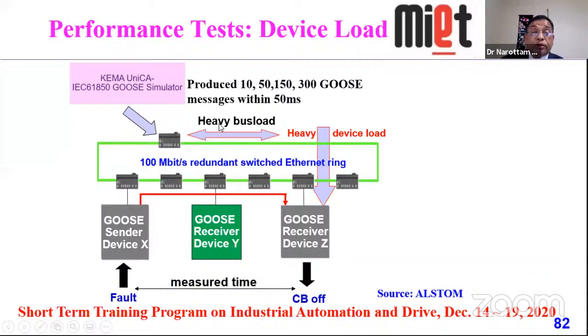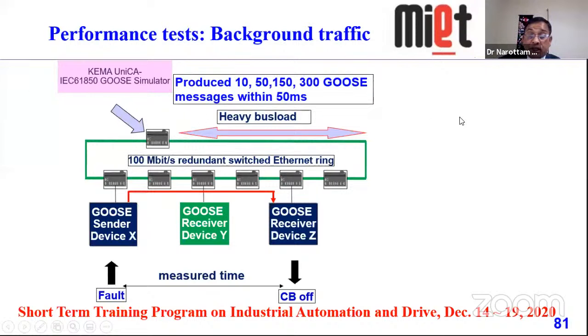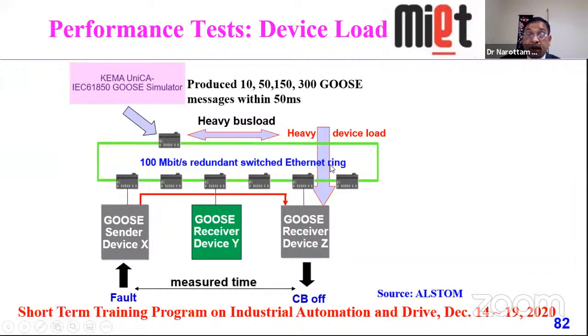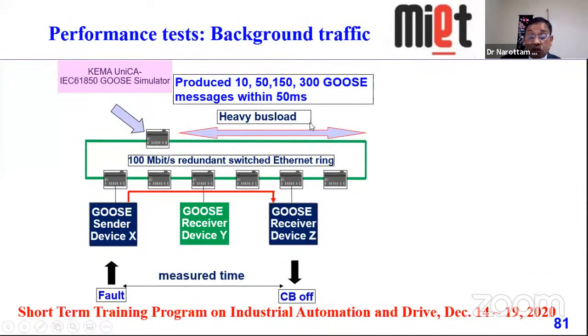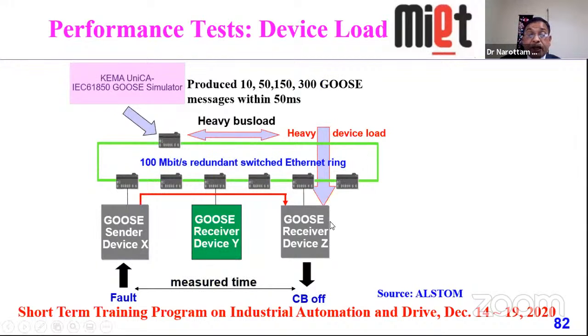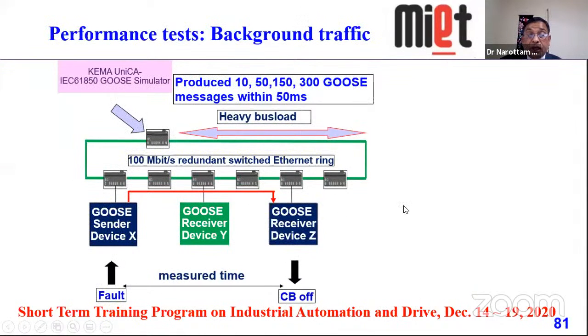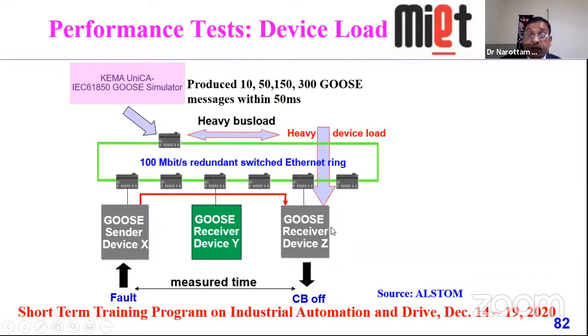Okay, and then we can, so far, yes. And now we are going for another set and then see the difference, because this is the simulator here, then this one simulator, and then heavy device load, because this is bus load, and this is heavy device load. Device is here. So far, in this case, also produce so many GOOSE messages within 50 milliseconds. And then heavy load is here, and then this is the fault, and then device receiver Y, this is device, and GOOSE receiver device in Z. If we compare here, we can see this is the heavy device load, and circuit breakers are off here.